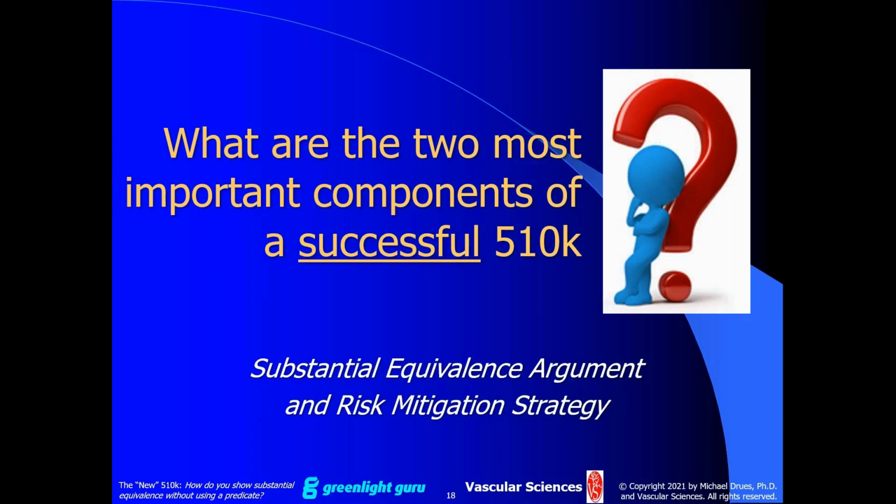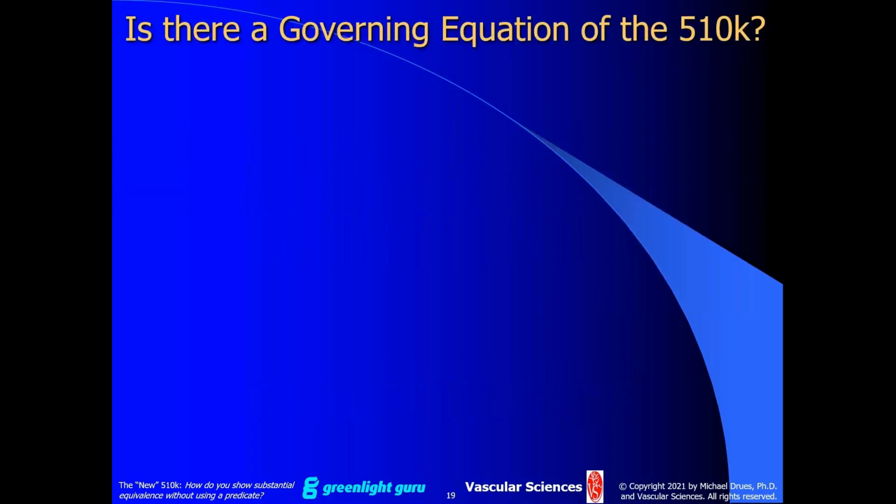So the question is, what has changed? Has the regulation changed? Absolutely not. The regulation for the 510K has not changed one letter, one word since it was created in 1976. Yeah, FDA has put out a number of guidances in the last almost 50 years, but the regulation itself has not changed. But what has changed quite a bit, and again, this is beyond the topic of today's conversation, is the level of scrutiny, if you will, that FDA is applying to certain portions of these submissions.